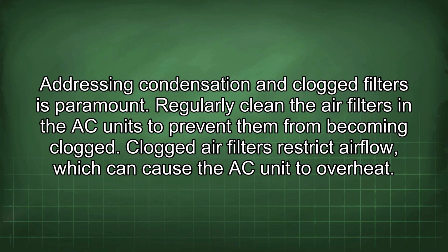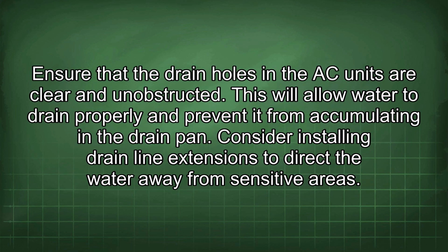Addressing condensation and clogged filters is paramount. Regularly clean the air filters in the AC units to prevent them from becoming clogged. Clogged air filters restrict airflow, which can cause the AC unit to overheat. Ensure that the drain holes in the AC units are clear and unobstructed. This will allow water to drain properly and prevent it from accumulating in the drain pan. Consider installing drain line extensions to direct the water away from sensitive areas.